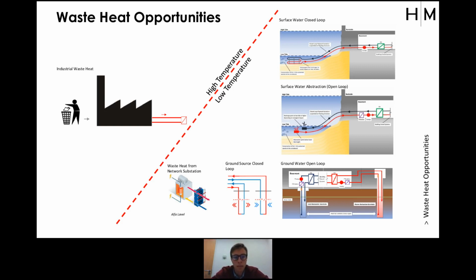So I would recommend, at the earliest possible stages, really looking into where the opportunities are, where you can find supplementary energy that will benefit your overall operating efficiency. But maybe also, at these very low temperatures, looking at a bivalent system design. So if you're using air source heat pumps in addition to these alternative heat sources, they operate very poorly and their capacity significantly reduces at these low temperatures.